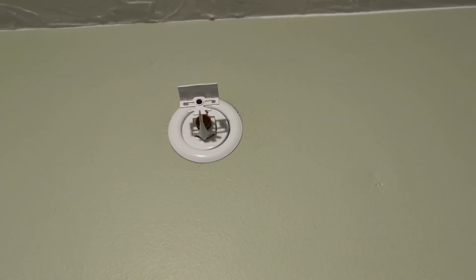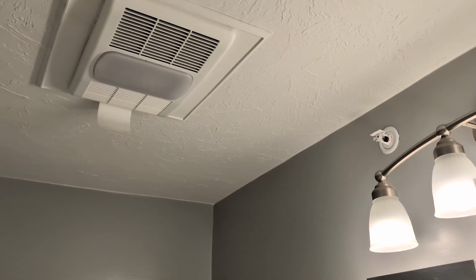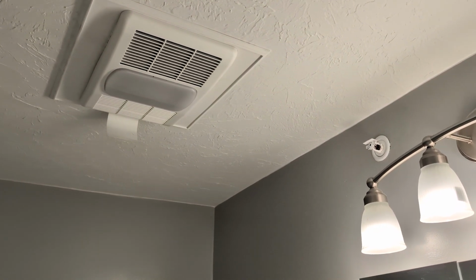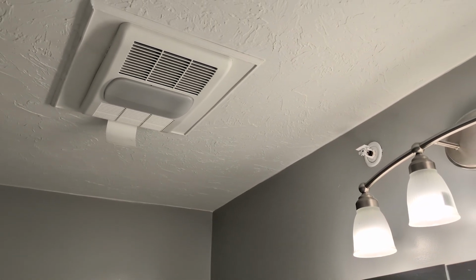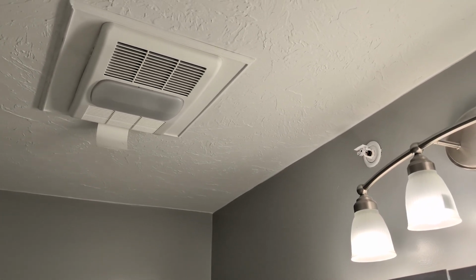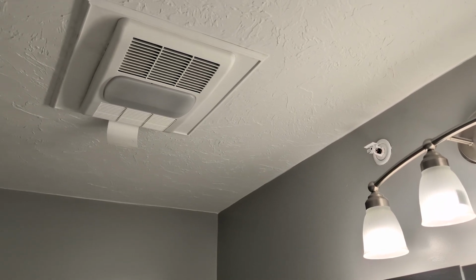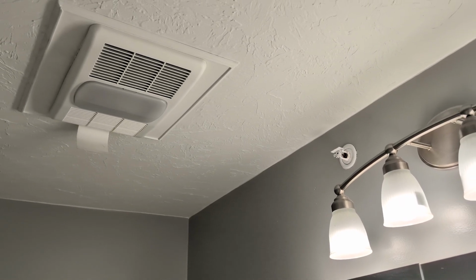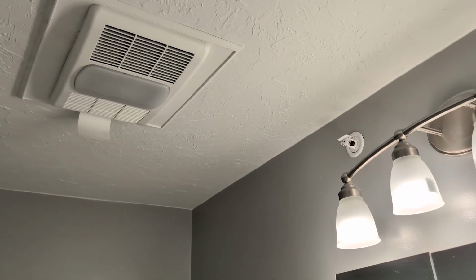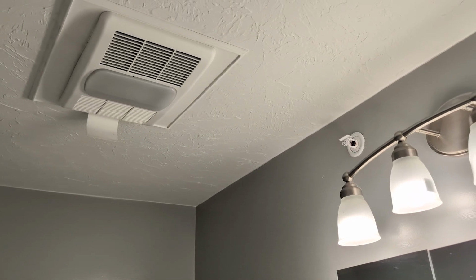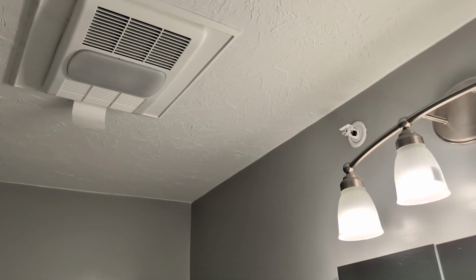People will ask if we are required to be putting sprinklers within closets. The answer is no. Sprinklers are not required in closets that are less than 24 square feet or 2.2 square meters, provided that the entire closet is lined with a non-combustible or limited combustible construction. Similarly to closets, bathrooms that are less than 55 square feet or 5.1 square meters are not required to be sprinklered. And that's because data shows that fires starting in closets or bathrooms are, first of all, very unlikely. And second of all, if they do occur, they don't lead to deaths within the home. So the added benefit versus the cost of adding the sprinkler in these spaces was seen to not be required as far as providing that life safety, which again is that goal of NFPA 13D.